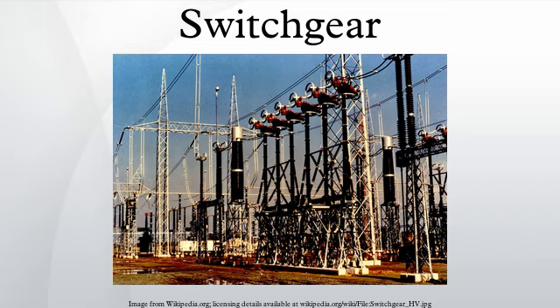The very earliest central power stations used simple open knife switches, mounted on insulating panels of marble or asbestos. Power levels and voltages rapidly escalated, making opening manually operated switches too dangerous for anything other than isolation of a de-energized circuit. Oil-filled equipment allowed arc energy to be contained and safely controlled. By the early 20th century, a switchgear lineup would be a metal-enclosed structure with electrically operated switching elements, using oil circuit breakers. Today, oil-filled equipment has largely been replaced by air blast, vacuum, or SF6 equipment, allowing large currents and power levels to be safely controlled by automatic equipment incorporating digital controls, protection, metering and communications.